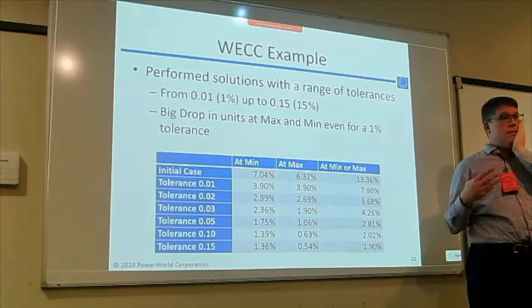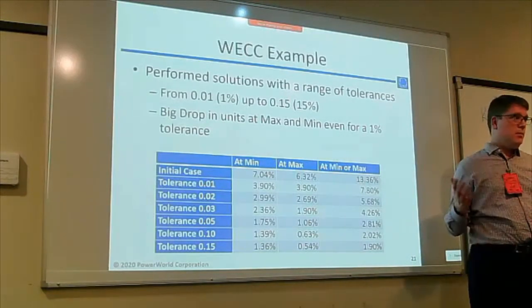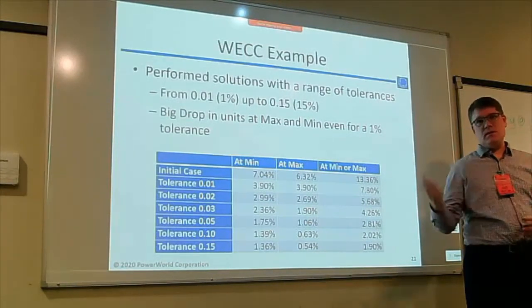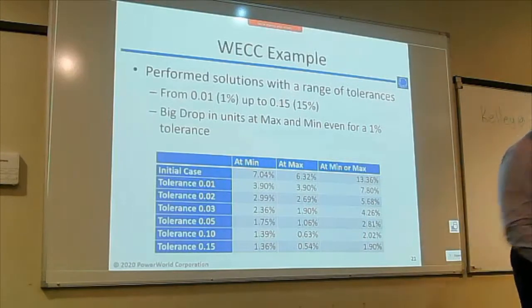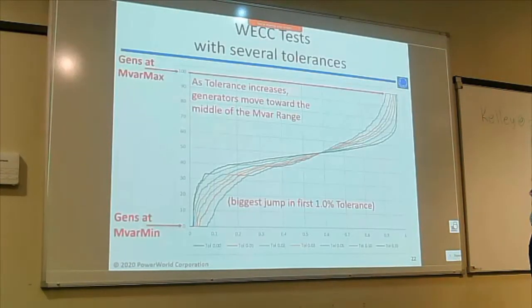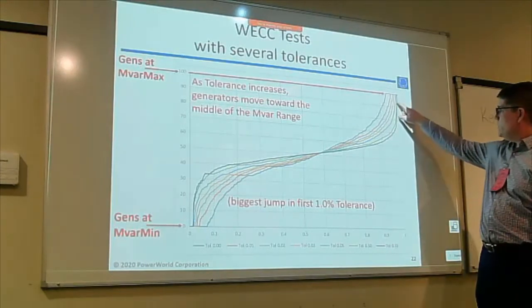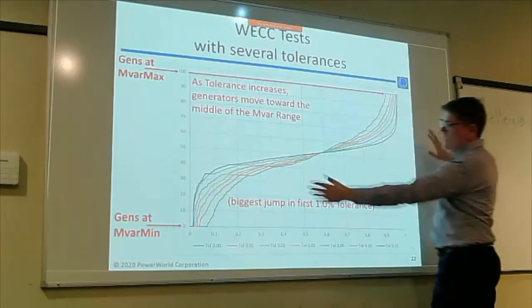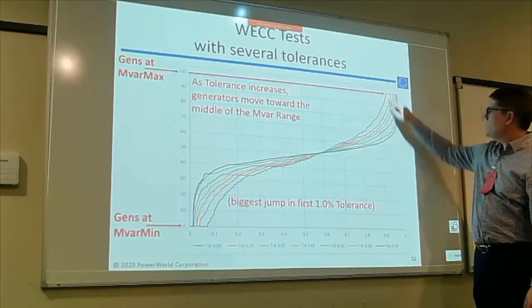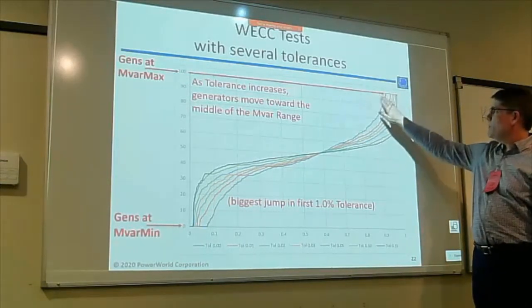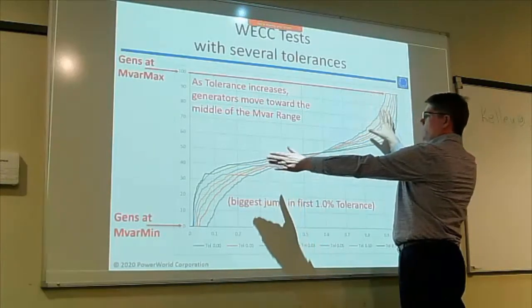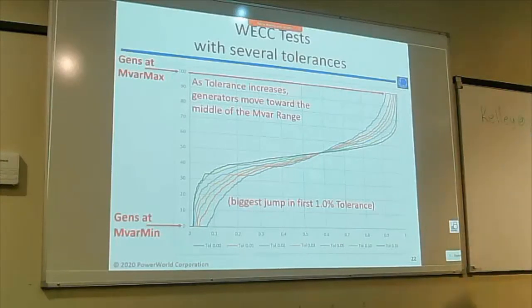But in the short run, I feel like this maybe is a good thing to do, like James was doing, where he was just trying to come up with better set points. What you could do is run this, and then when you're all done, take the voltage at the regulated bus, copy that over to the set point, and set the tolerance back to 0, so you can then share it with other people, and they're still back where they were, but you mucked around with your set points. You'd have a better initial state for the transient. I don't know this until hundreds of people start using it, but I think the power flows in general will be a little bit better, even post-contingency solutions.